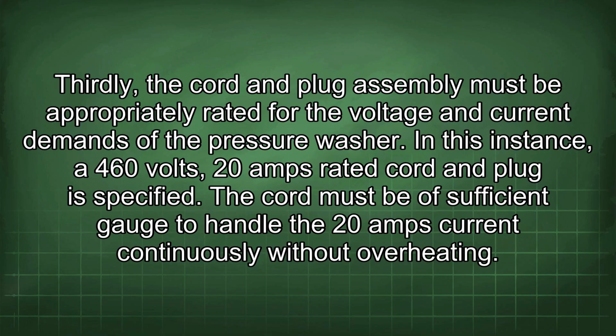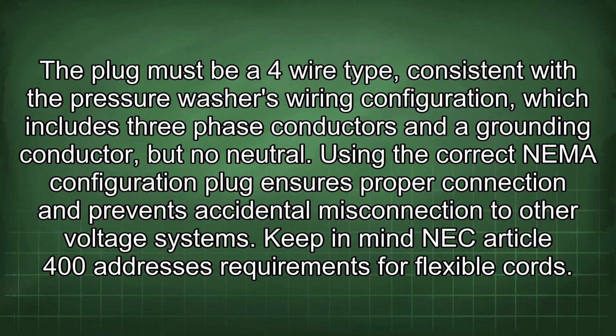Thirdly, the cord and plug assembly must be appropriately rated for the voltage and current demands of the pressure washer. In this instance, a 460 volts 20 amps rated cord and plug is specified. The cord must be of sufficient gauge to handle the 20 amps current continuously without overheating. The plug must be a 4-wire type, consistent with the pressure washer's wiring configuration, which includes 3-phase conductors and a grounding conductor, but no neutral. Using the correct NEMA configuration plug ensures proper connection and prevents accidental misconnection to other voltage systems. Keep in mind NEC Article 400 addresses requirements for flexible cords.